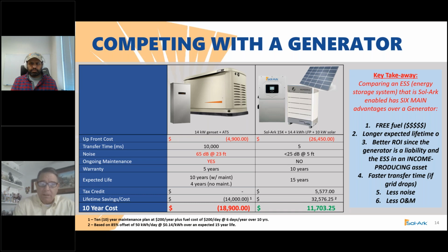So if you look here on this slide, this is the contrast. It's a 14 kilowatt genset, the ATS from Generac. Let's go down this first column: the upfront cost is about $5,000. The transfer time is 10,000 milliseconds. That's a big number, but actually that's about 10 seconds. Count to 10 in your head, it's not a long time, but it's certainly not fast. It's super noisy, it sounds like a plane trying to take off, and it has a lot of maintenance aspects.